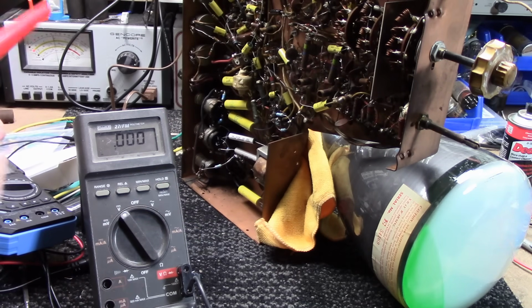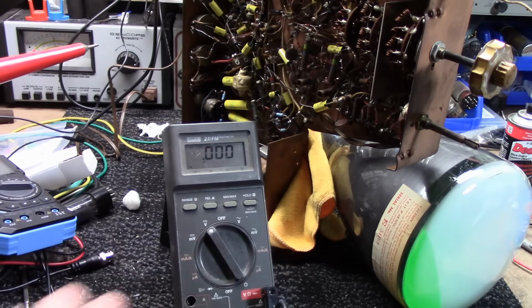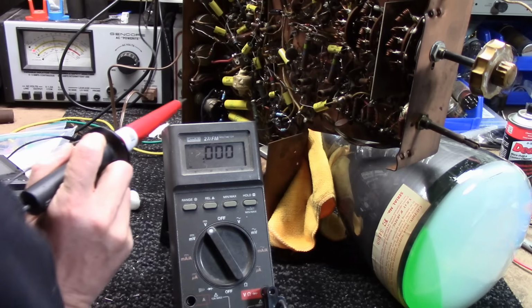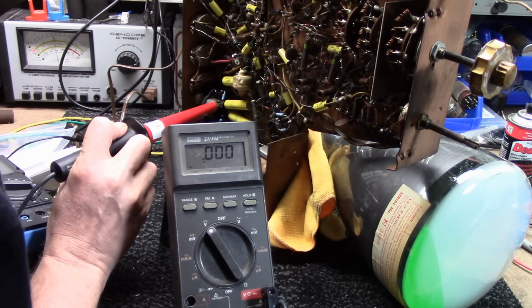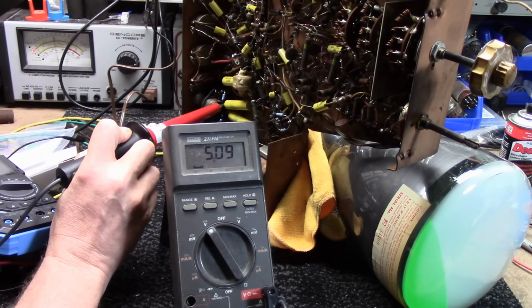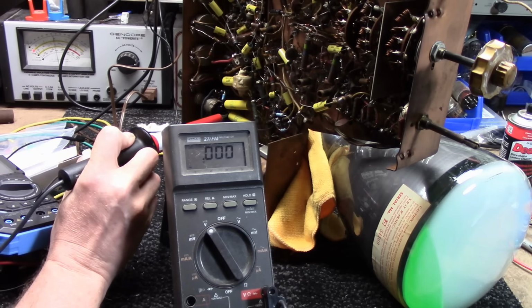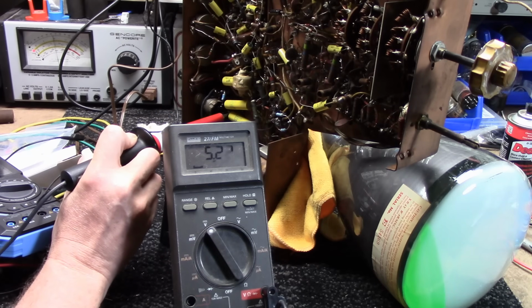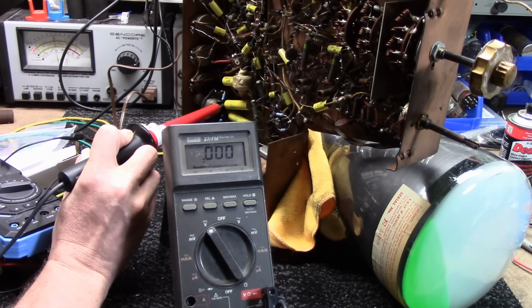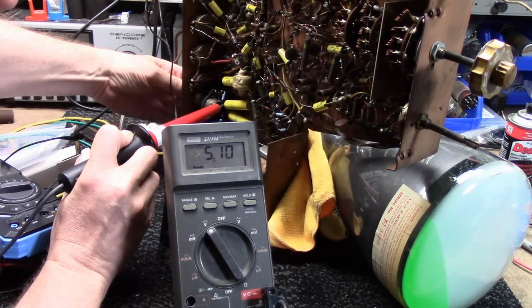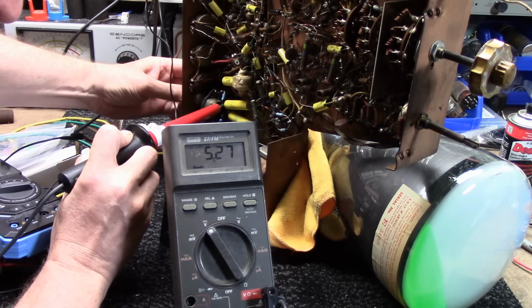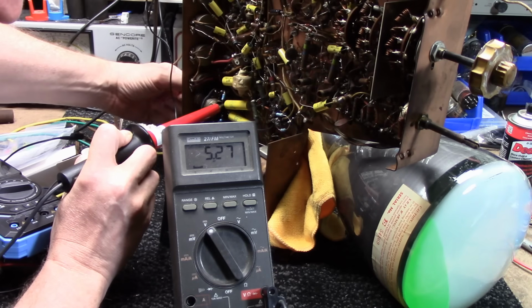Let's see. So I've got a high voltage probe going to my trusty Fluke 27. Here is one deflection plate. I could hear it screaming as I got close to it, so we got 5,000 volts there. Well, that's not what I wanted to see. I mean, it's good and bad, so yes, we do. And this should vary slightly as I vary the offset controls. I got 5.1, 5.3. So, nuts.